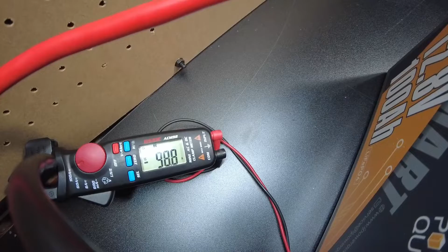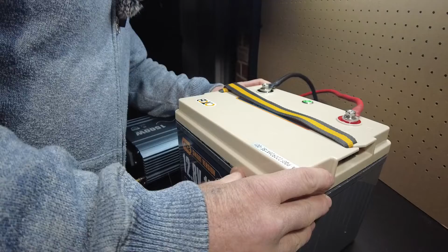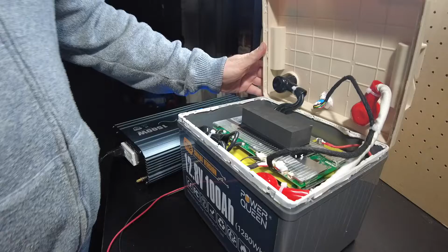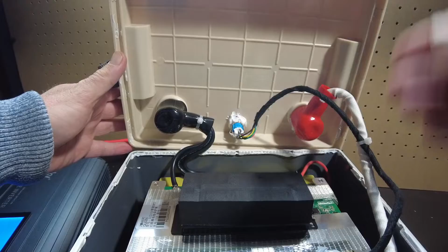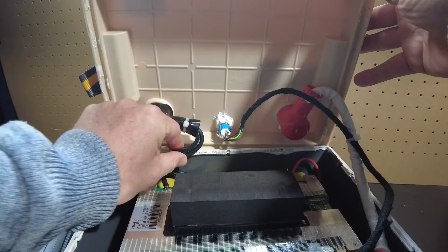Okay, well, we are pulling 99, almost 100 amps. So that's good. Now what we're gonna do is let that run and see, yeah, so we're at 99.5 amps. I'm gonna see if anything gets overly hot in here, because we're kind of wondering if these wires will actually do the 100 amps.